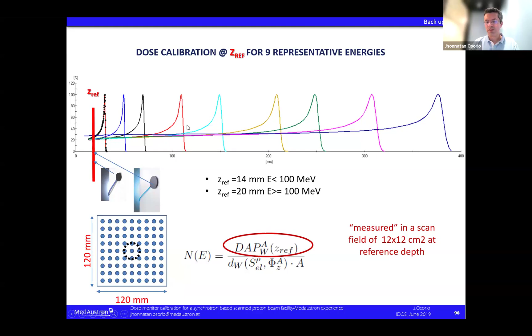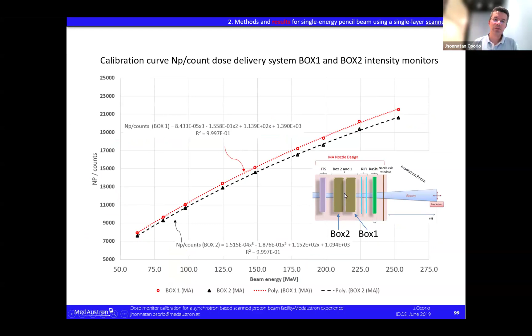We need to put the reference chamber in the plateau region in order to avoid high gradients in the dose. We need to calibrate the machine at several sets of energies. One of the calibrations that I did is to calibrate the monitor chambers in terms of number of particles per count, but this depends on the energy. So you have a polynomial, it's not only one energy.